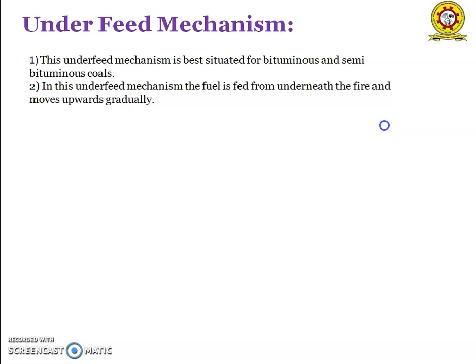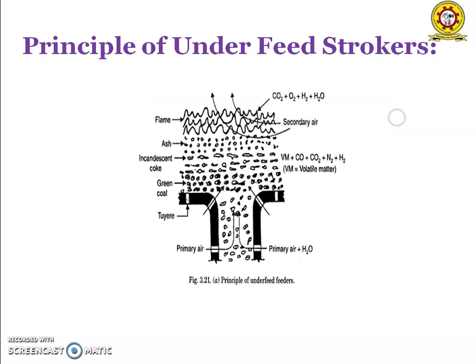And the under feed mechanism. This under feed mechanism is best suited for bituminous and semi-bituminous coal. In this under feed mechanism, the fuel is fed from below the fire and moves upward gradually. The air entering through the grate openings comes in contact with the raw fuel and mixes with the volatiles released from the raw fuel and enters into the combustion chamber. This is the basic principle of the under feed stoker.